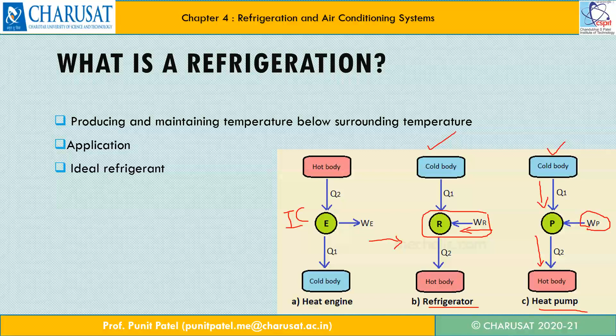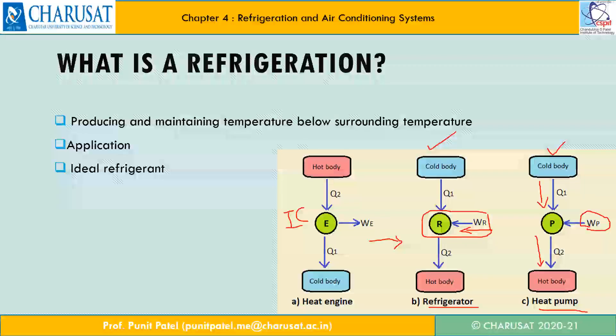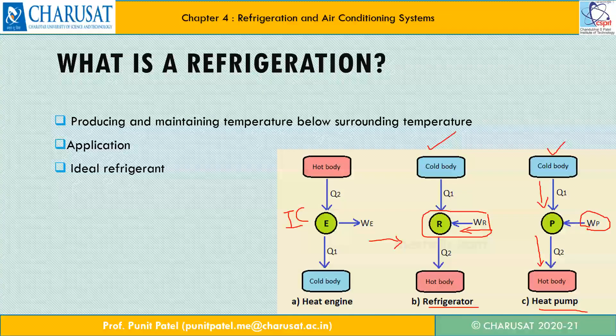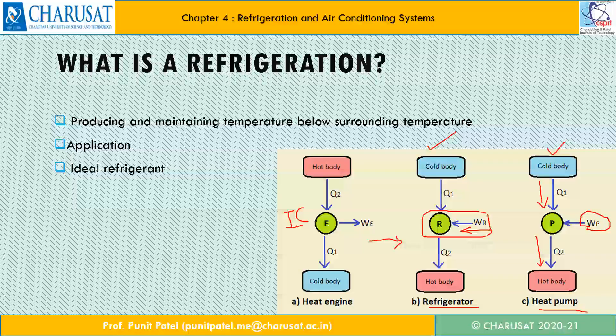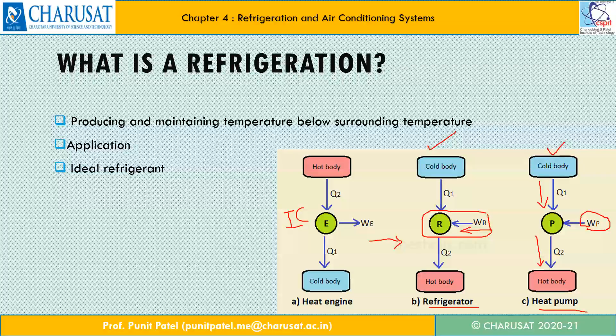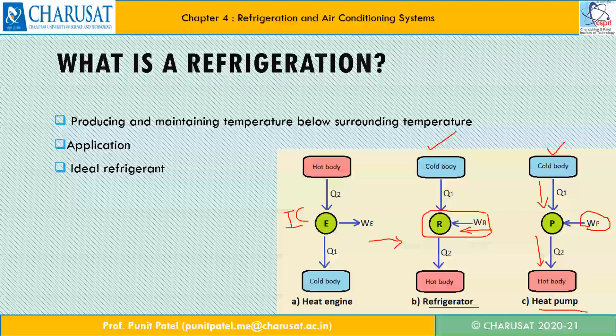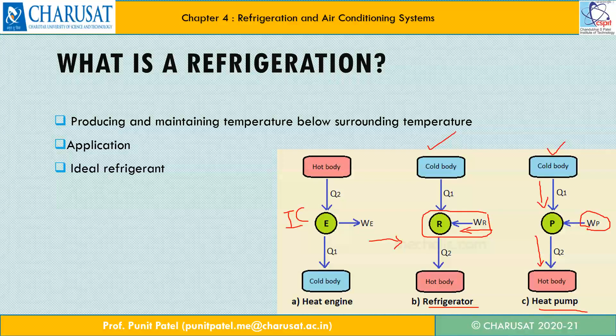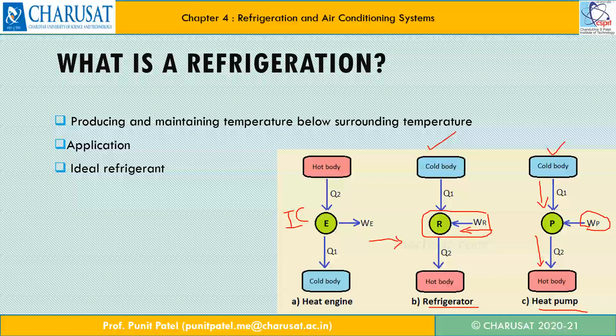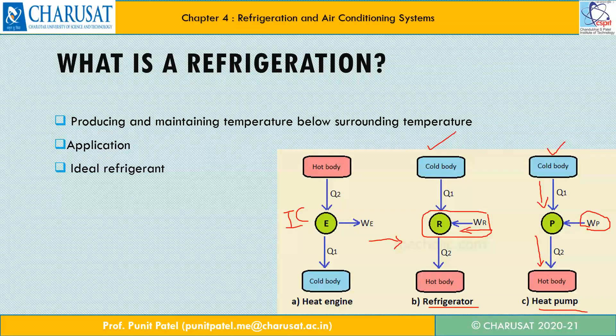Before we talk in detail, let us talk about the ideal refrigerant — meaning, if we want to design the refrigerating system, which kind of properties should we have in that particular refrigerant. It should have high latent heat of vaporization and low specific volume. It should have good thermal conductivity for rapid heat transfer. It should have low specific heat in liquid state and high specific heat in vapor state. It should have a low saturation pressure, a high coefficient of performance, and it should be economical in cost.